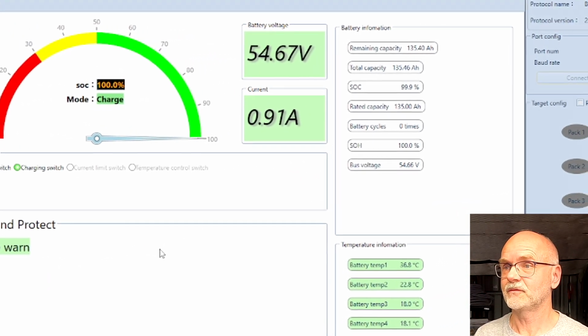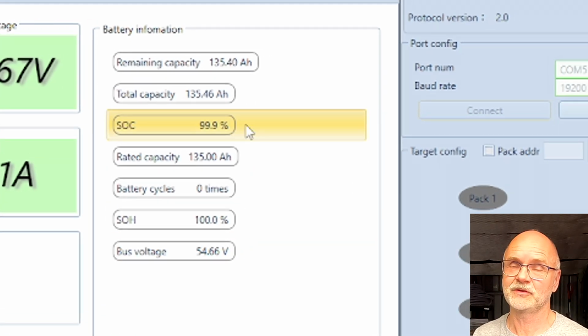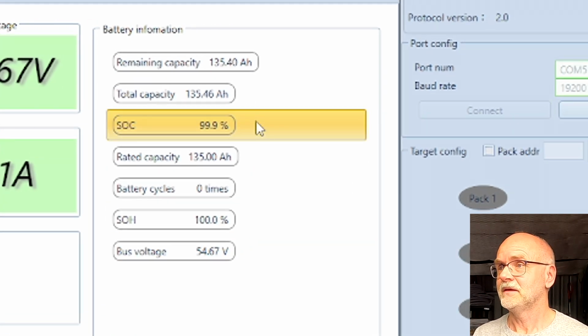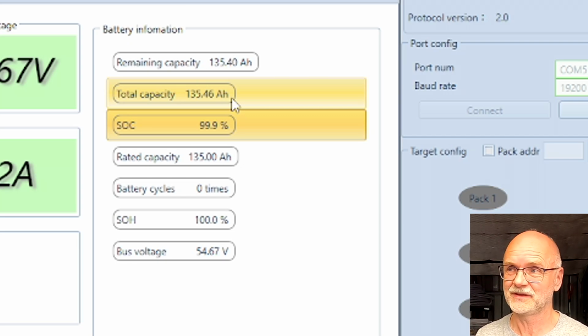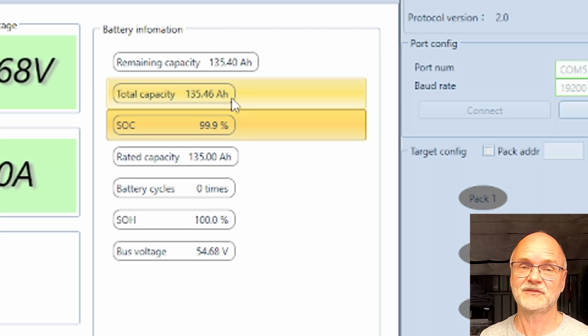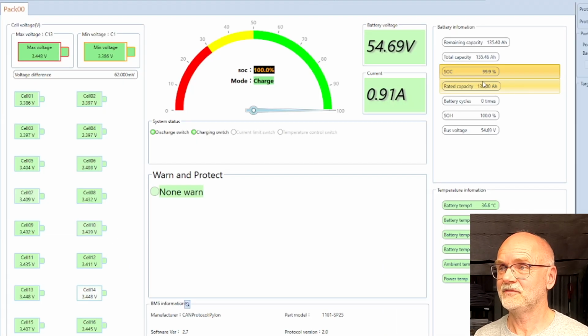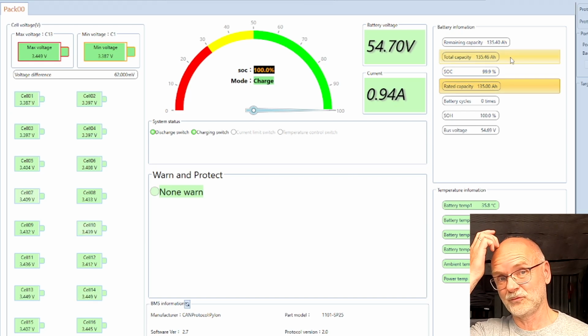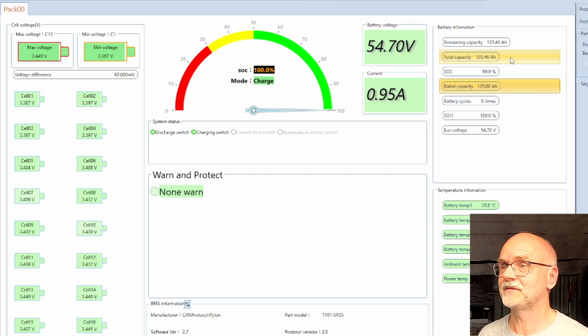The state of charge of the battery says 99.9%, and it has a total capacity of 135.46 ampere hours. I'm not sure how this is being calculated, because I set 135 ampere hours as the nominal capacity in the settings. There it is, rated capacity, 135. But it claims the battery has 135.46, which I doubt it has.